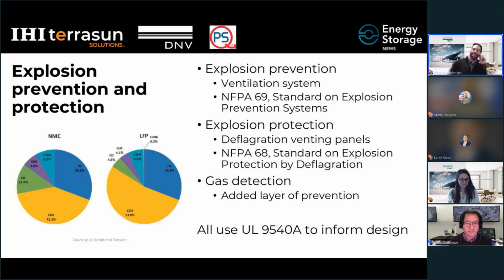Yeah, so as Carrie said, UL9540A should not be used to determine if a battery is, quote, safe. When UL9540A testing happens, you have to remember that the test method used to send the battery into thermal runaway is not the sole failure method or fire risk associated with the BESS unit. Often a cell heating method is used to induce thermal runaway, but the battery could behave differently if the cell is penetrated, if there's an electrical fire within other parts of the container, or if there's an HVAC system failure. These aren't considered by UL9540A.